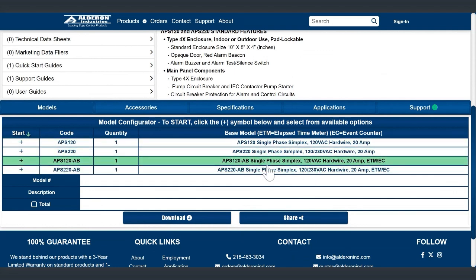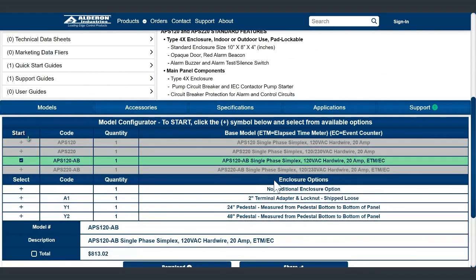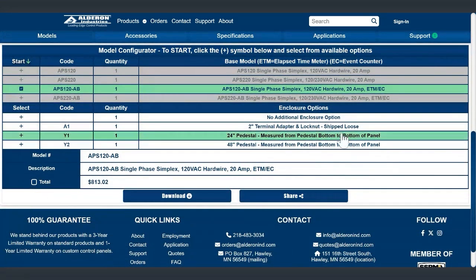So let's just say, yeah, we want both the elapsed time meter and the event counter, 120 volt. You can do a 2-inch terminal adapter and lock nut, which is shipped loose, separate, and that just goes on the bottom of the panel. They just drill their own hole. This is rated 4X for outdoor use. We can't install the lock nut unless we bought like a $100 4X rated plug, but then that just increased the cost a lot, too much. So we ship it loose, and then you just drill your 2-inch hole in the bottom, and then hook it up to your conduit. You can also get it with a 2 foot or a 4 foot pedestal, and that's measured from the bottom of the panel to the top of the base of the post, the pedestal.